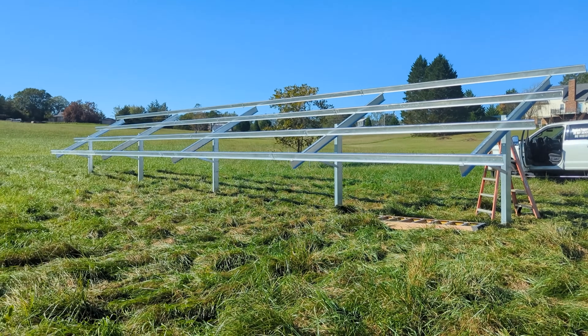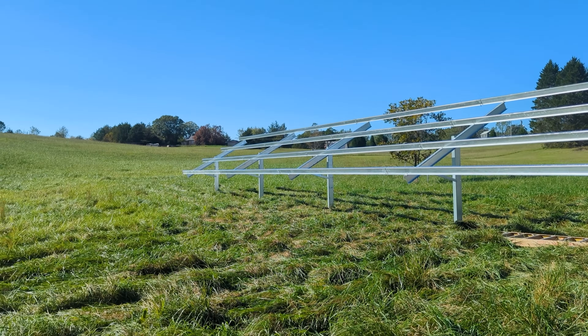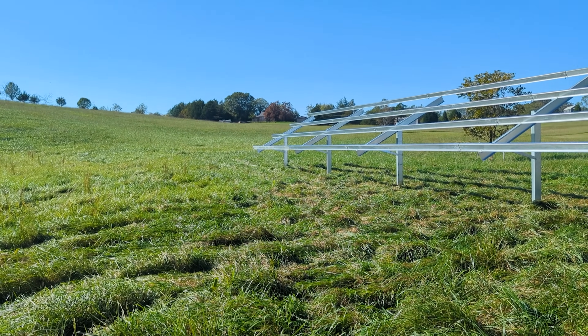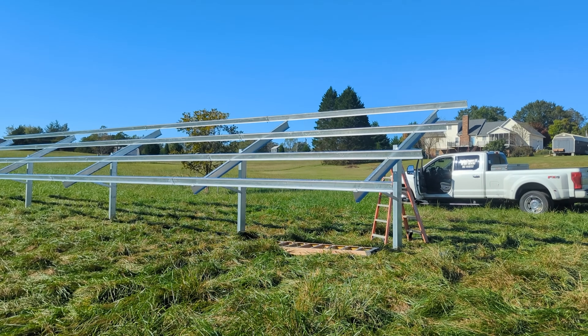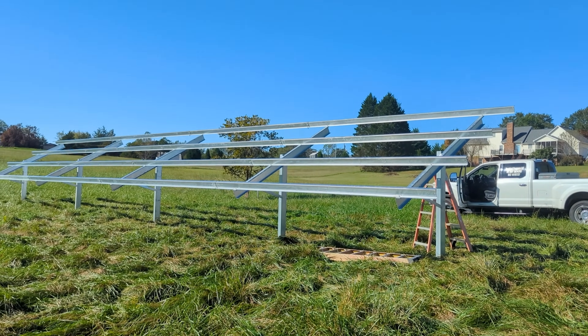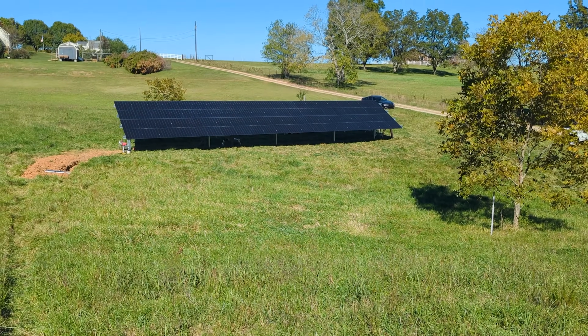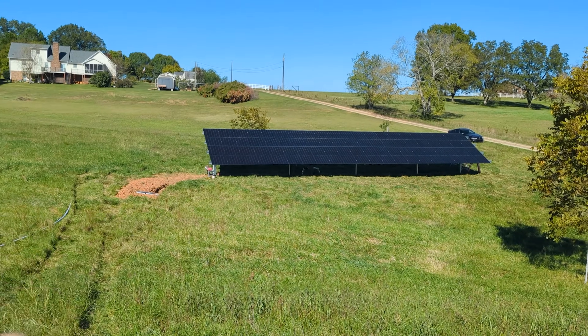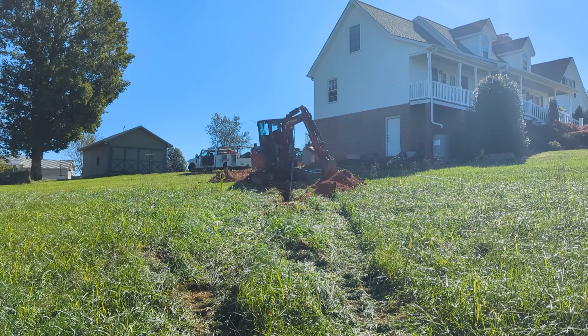Slightly canted west — azimuth about five degrees west — just for the air conditioner here in the afternoon, which is usually the heaviest load, so we tilt it over just a little bit. Thirty degrees fixed tilt, Sinclair racking — bulletproof. We're back, just finished racking the glass and got some conduits started. Tony's in the excavator finishing up the trenching.